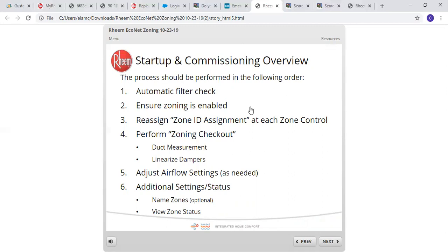You will have an automatic filter check. Ensure zoning is enabled. Reassign zone ID assignment at each zone control. Perform a zoning checkout, full duct measurement, and linearize the dampers. At that point, you can fine-tune and adjust the airflow as needed. And additional settings and status: you can name zones and view the zone statuses as well.